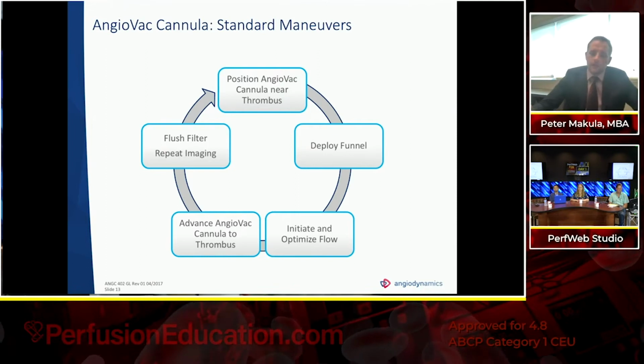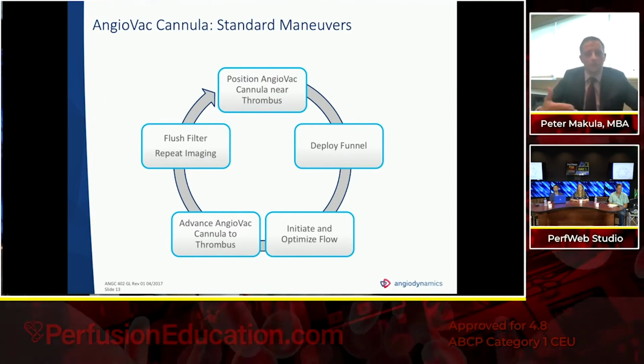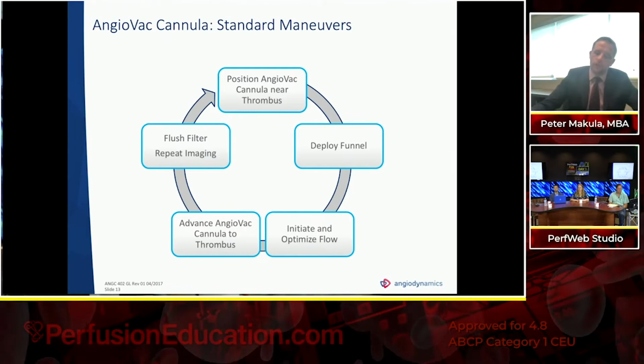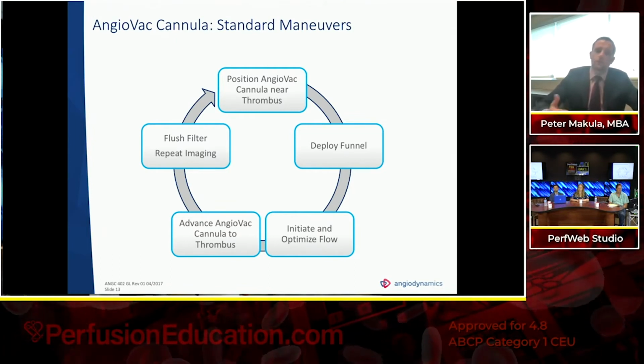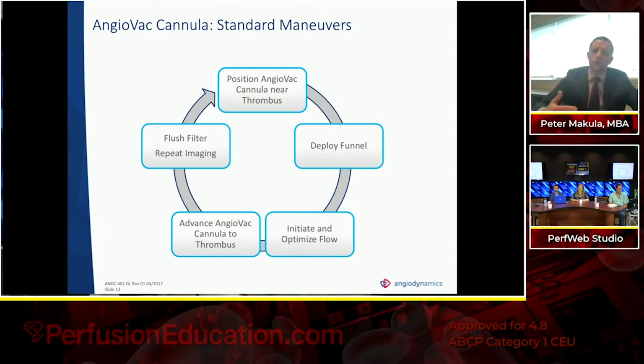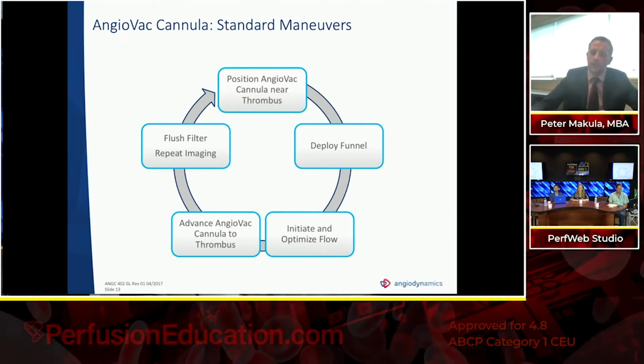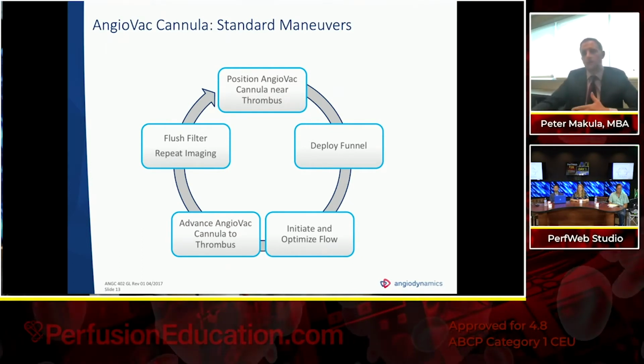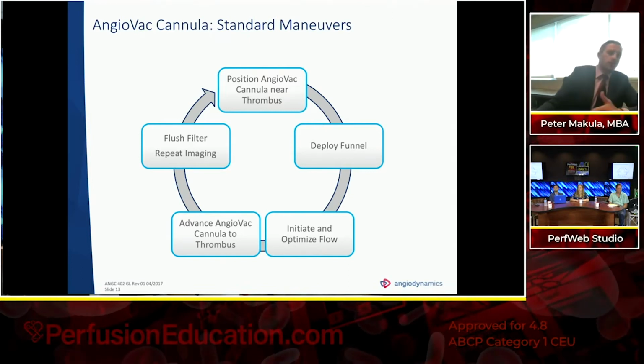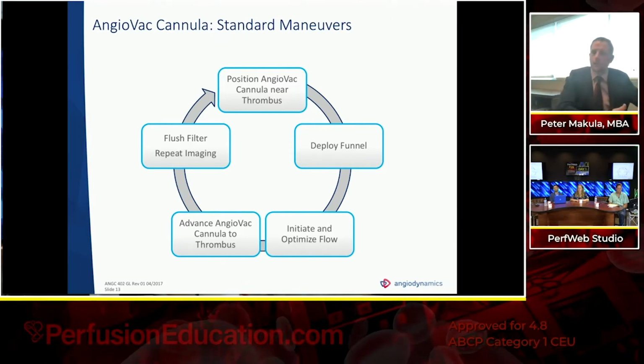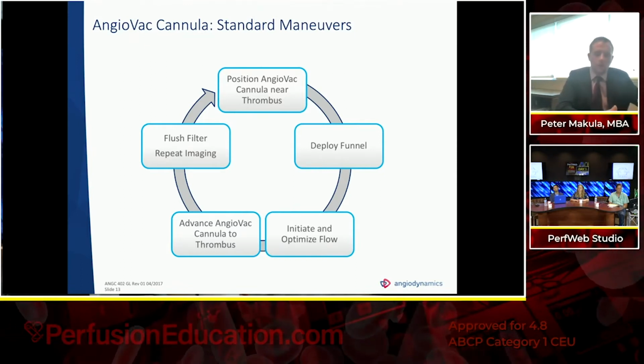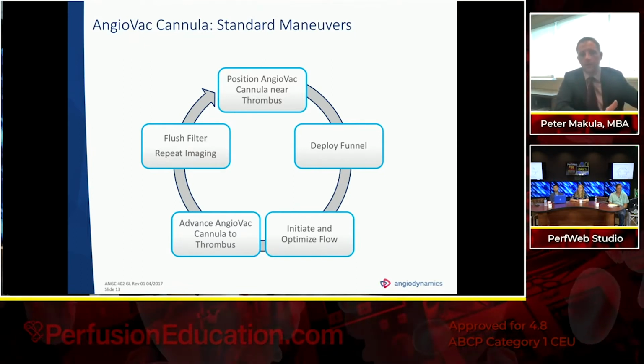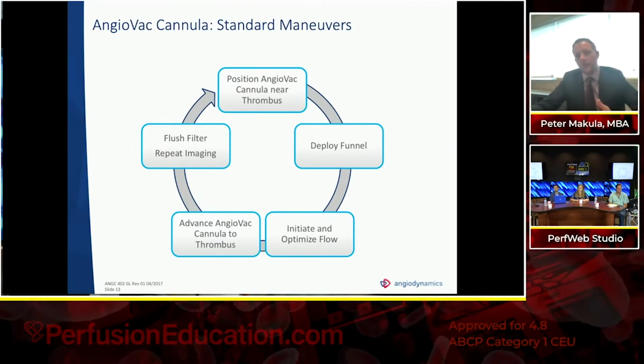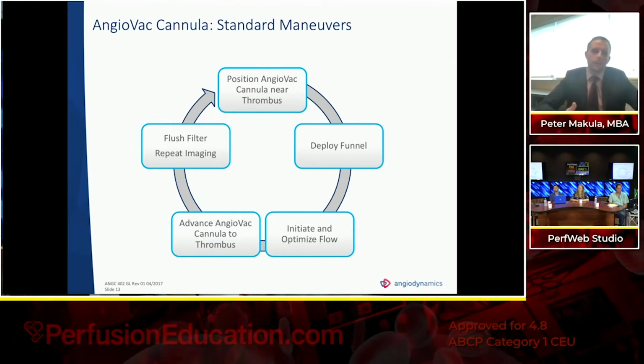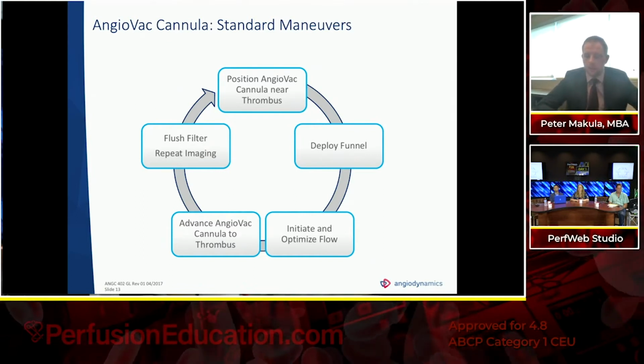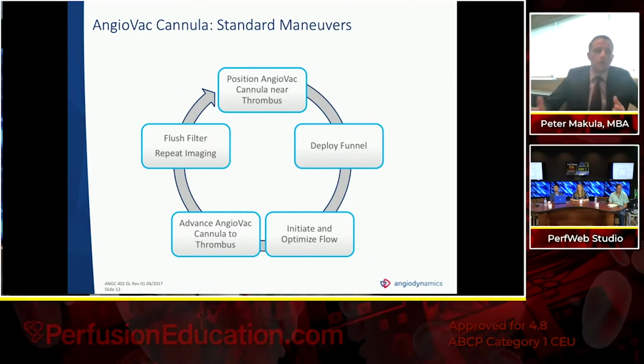And that's different than the cavitation of a vessel if the negative pressure may be too high. What you'll see with cavitation of the vessel is a much more rhythmic collection and release of the negative pressure. And that allows you to understand the difference between engaging actual material you're trying to remove and aspirate, and whether the negative pressure is too high and actually collapsing the vessel. If that occurs, all we really need to do is back off the negative pressure slightly to maintain the highest negative pressure we can without risking closing the vessel. And the reason for that is really flow is our friend here.